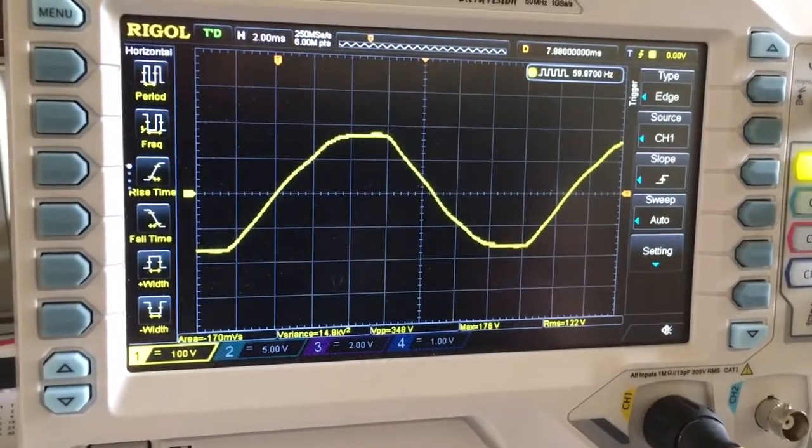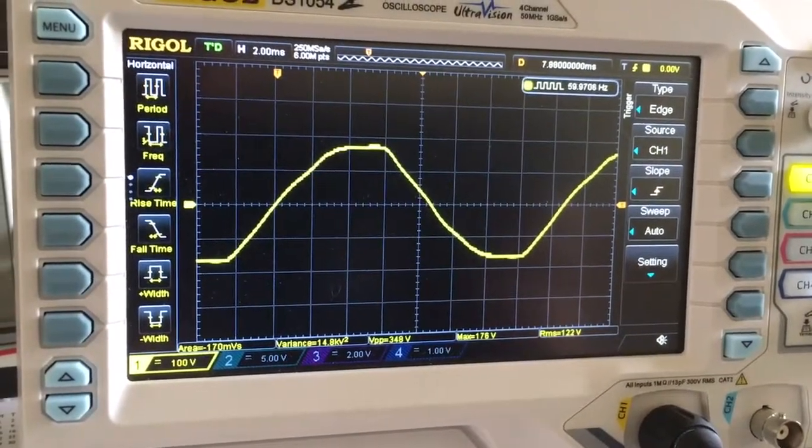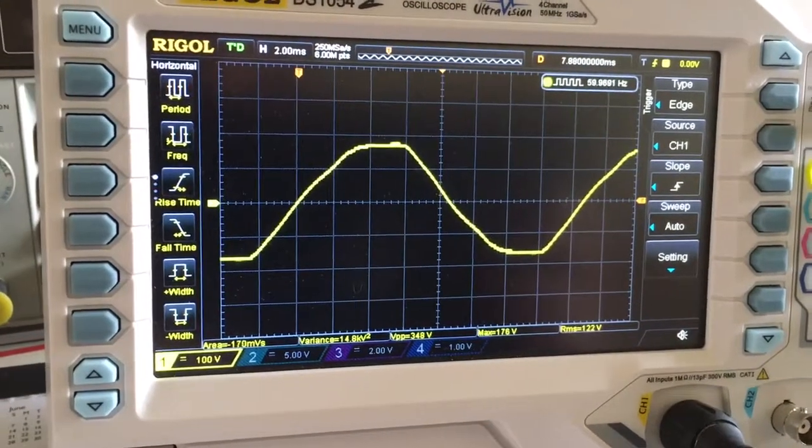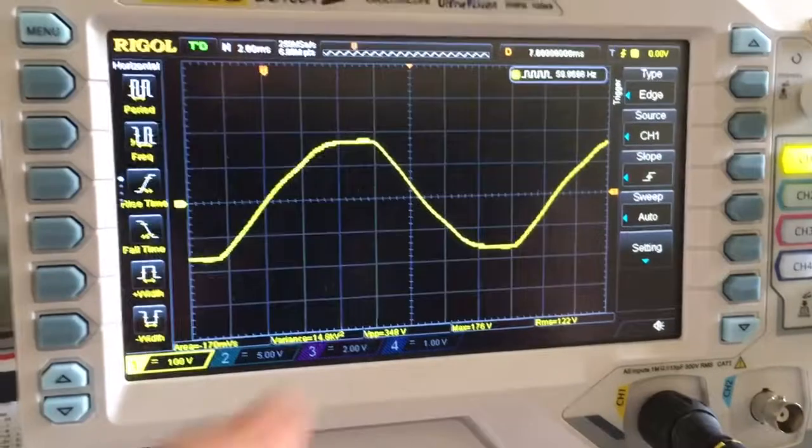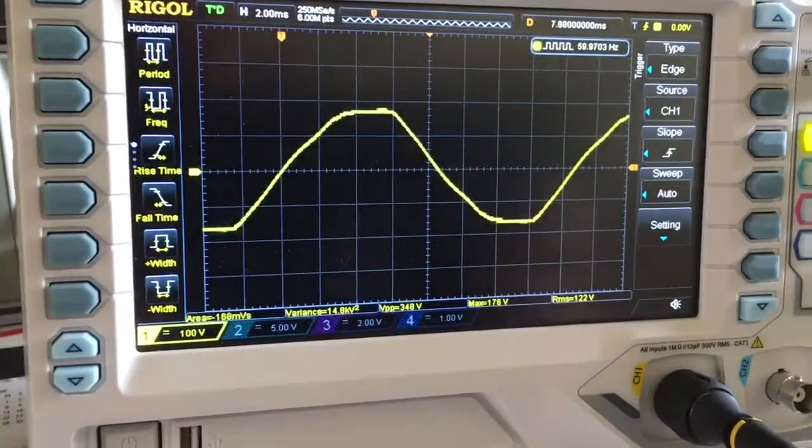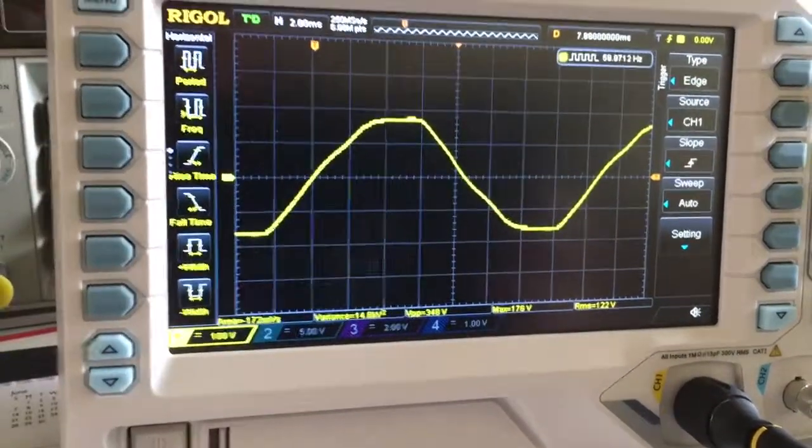From the grid, or from the power system, so it takes a large piece of equipment to do the outbound transmissions. The inbound transmissions from the meters are small glitches of about 100 amps that show up as tens of volts or so near the zero crossings. Again, these are all outbound signals you're seeing now.